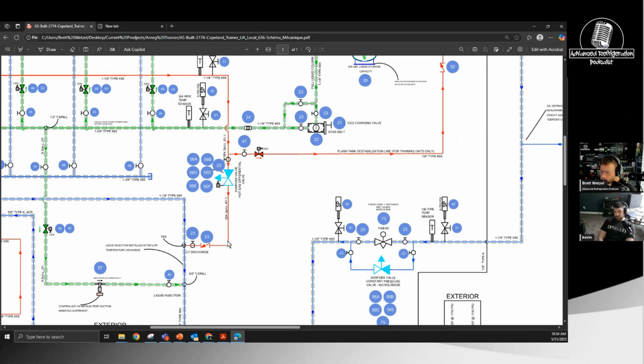Like, this would fix a lot of the Carnot issues where you're running compressors at 500 pounds when you could be running them at 400 pounds. You drop the pressure 100 pounds by changing this Danfoss valve around. This is great. So it's just boosting the discharge pressure. Yep, boost it up to above the flash tank. So I think it's 20 pounds above the flash tank is what they were shooting for. Only 20? 20. It's a trainer.